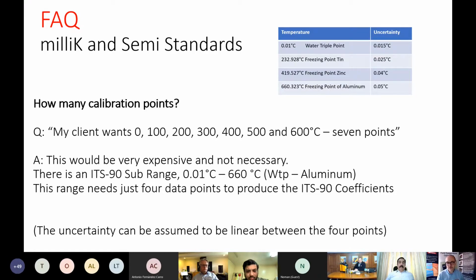And then when we're talking to customers, the question we always get is, well, how many calibration points do I need? And the client might say, I want 0 degrees, 100, 200, 300, 400, 5, 6, 7 points. And we could do that, but it would be unnecessary, because the ITS90 sub-range over this range is 0.01, the water triple point, to the freezing point of aluminium at 660. And we just need 4 data points. So to produce those ITS90 coefficients, we need 4 data points. And we can assume that the linearity, we can assume the uncertainty will be linear between these 4 points.